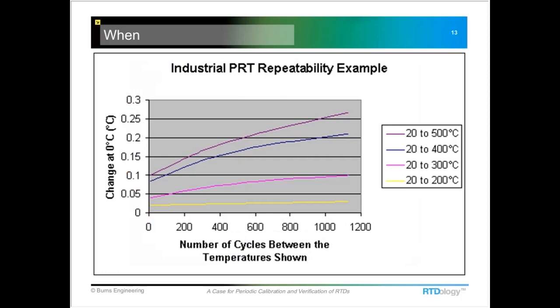I mentioned repeatability. When we have temperature cycling, as the temperature goes up, that repeatability is going to drop, and we're going to have a little more error. For example, if we look at that 20 to 500 C range, the top line on the graph, we can get about a quarter of a degree C just in repeatability. That gets worse as the temperature cycling goes on, and if you're running at a high temperature like that, the drift comes into play. So there are all these little error sources which you need to take into consideration.